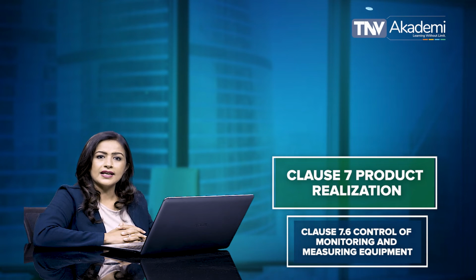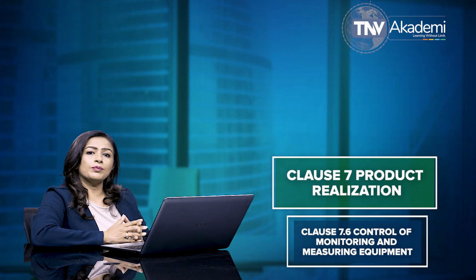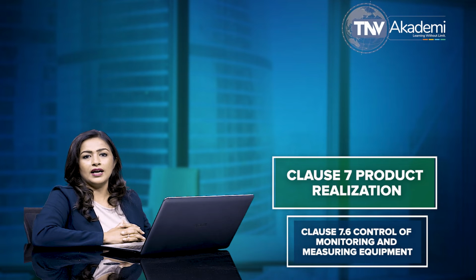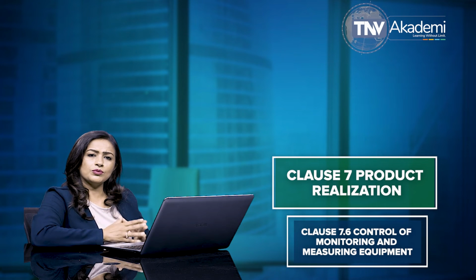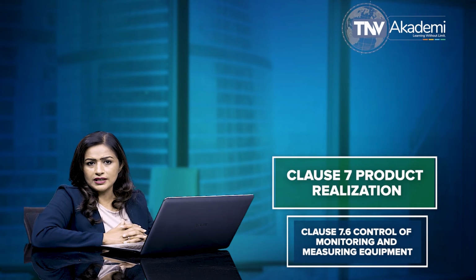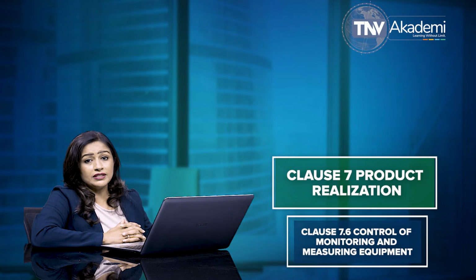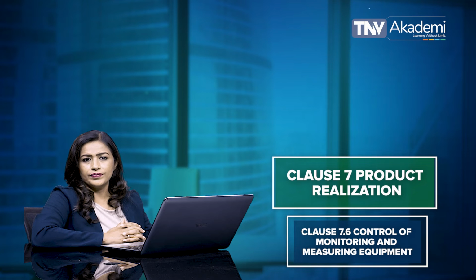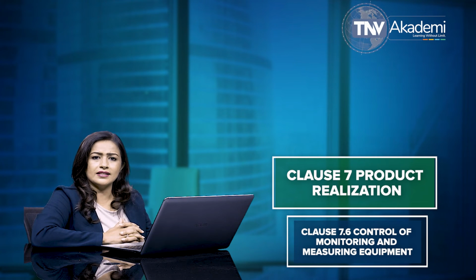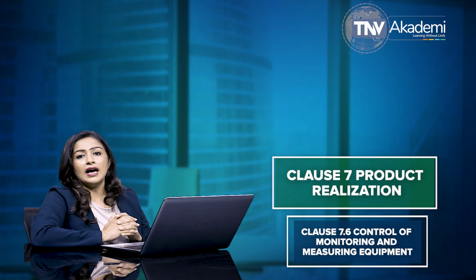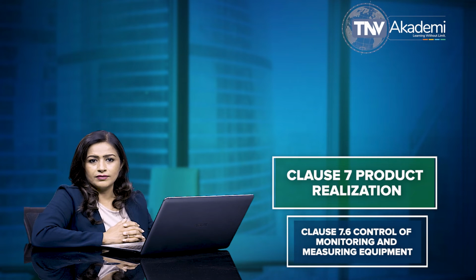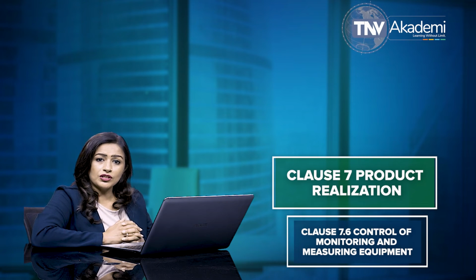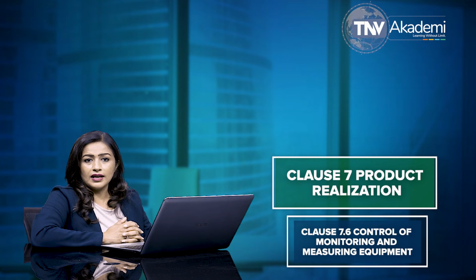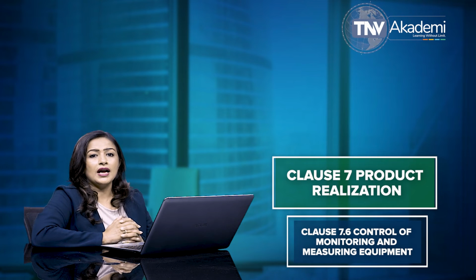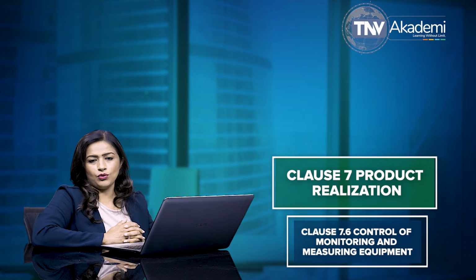As per subclause 7.6, as necessary to ensure valid results, measuring equipment must be calibrated or verified, or both, at specified intervals or prior to use against measurement standards traceable to international or national measurement standards. When no such standards exist, the basis used for calibration or verification shall be recorded. Measuring equipment must be adjusted or readjusted as necessary. Such adjustments or readjustments shall be recorded. Measuring equipment must have identification in order to determine its calibration status. Measuring equipment must be safeguarded from adjustments that would invalidate the measurement result, and must be protected from damage and deterioration during handling, maintenance, and storage.